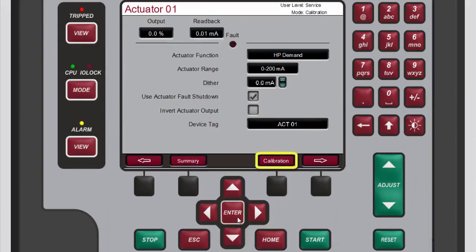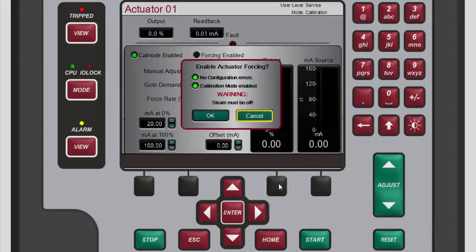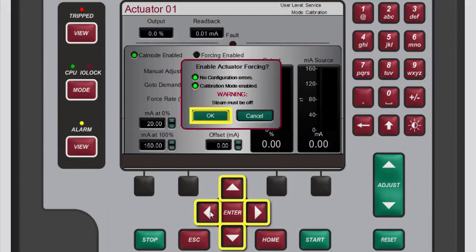Notice the new calibration button on the screen's menu bar — this appears because you are logged into calibration mode. Press the black function key below calibration. Forcing allows the controller to issue an output value, which makes it a good tool to use when calibrating and troubleshooting. To enable forcing, press the black function key below forcing. In the pop-up window that opens, verify that the LEDs for both permissives are illuminated green, then use the navigation cross keys to highlight OK and press enter.